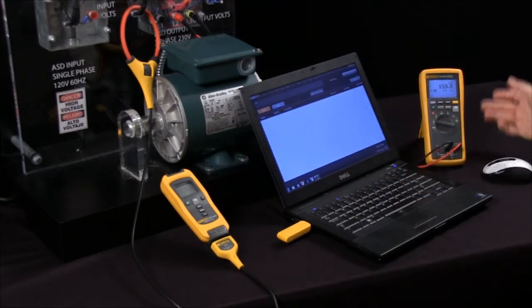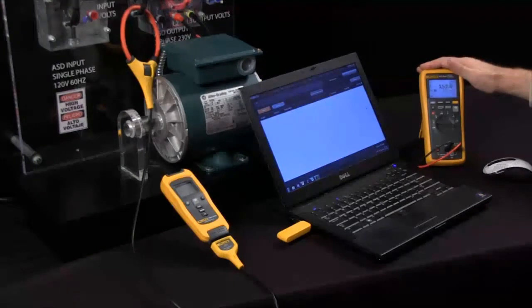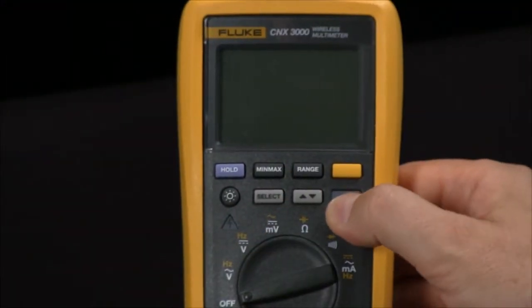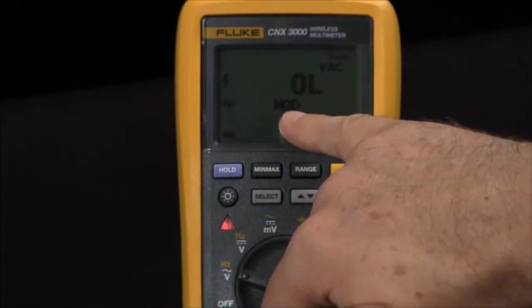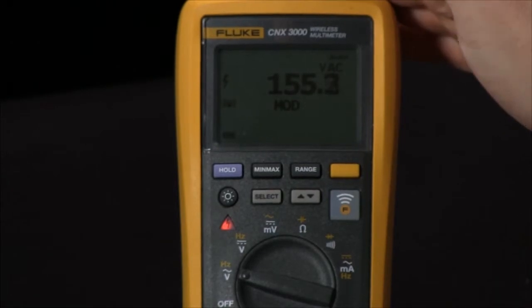Another nice feature: I can change this from a receiver to a module. By turning off the device, I hold down the receive button and turn the meter back on. You will see the screen fire up and display 'mod,' letting you know it is in modular mode.